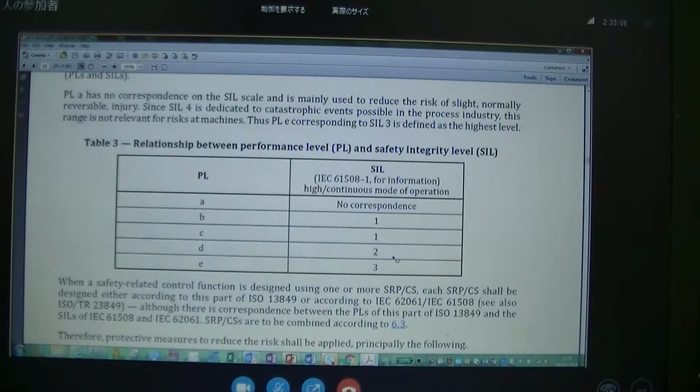When you or your customer has performed the calculation with SIL formulas, with a SIL 3 calculation you for sure also reach performance level E. But because of the simplified method to calculate performance level, with the result of performance level E, it is not 100% guaranteed that you reach SIL 3 with the SIL calculation.